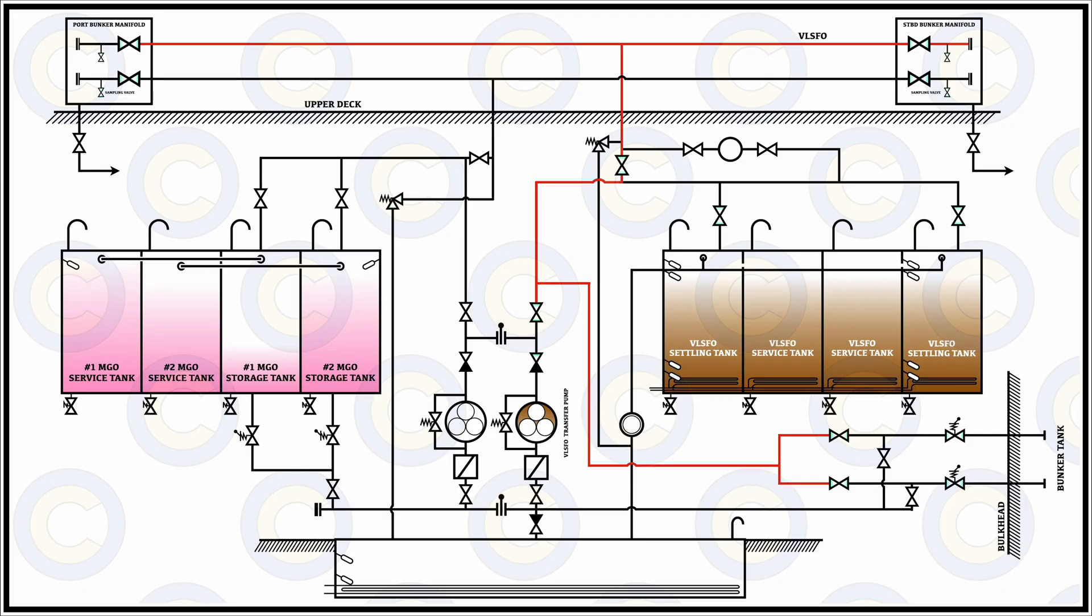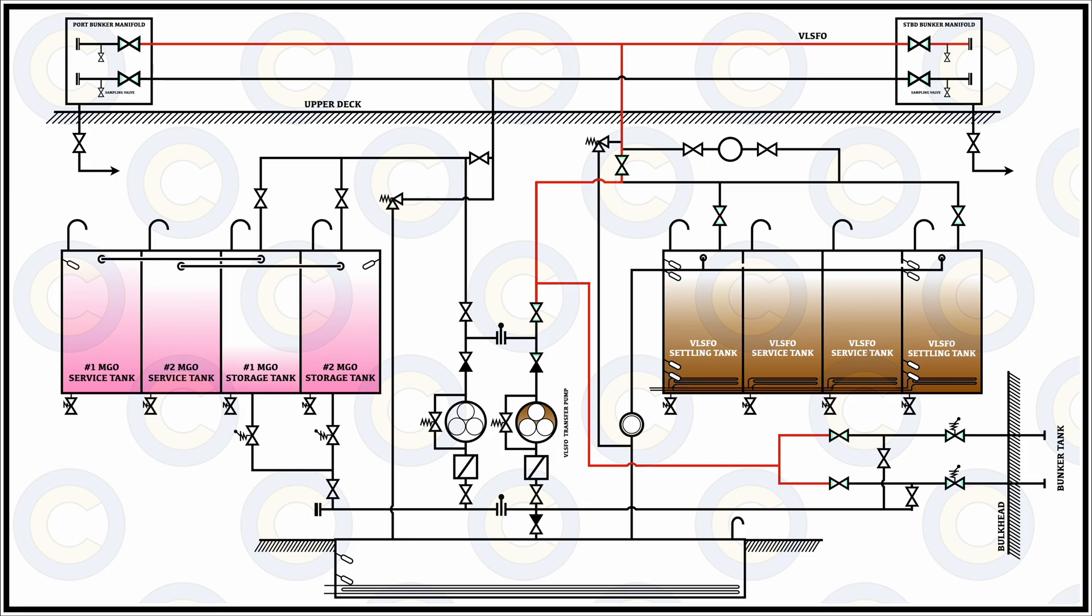On the latest vessels you will be having automatic valves as well in addition to manual valves, and these automatic valves would be either hydraulically or electronically operated from a remote location such as the master control room or the engine control room, or even on some vessels you will be having dedicated bunker control stations. From there you can electronically or hydraulically operate these valves, and this oil will flow and go into the dedicated bunker tank.